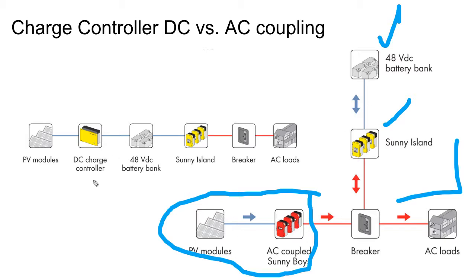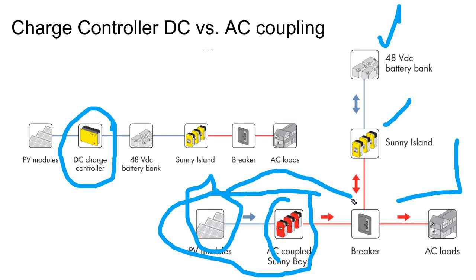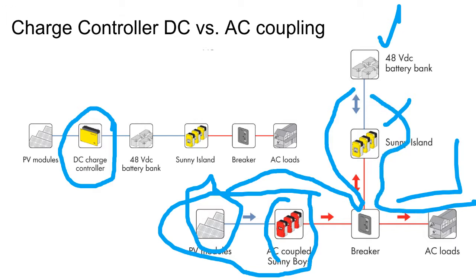And the cost difference, technically the charge controller should be cheaper than the inverter because it's just doing a DC to DC voltage regulation. It's not doing a full-blown DC to AC voltage regulation. And technically, the charge controller should be more efficient because in this case, we're going from our solar voltage, stepping it down to grid voltage, and then reprocessing it through our battery bank, and then reprocessing out of our battery bank.